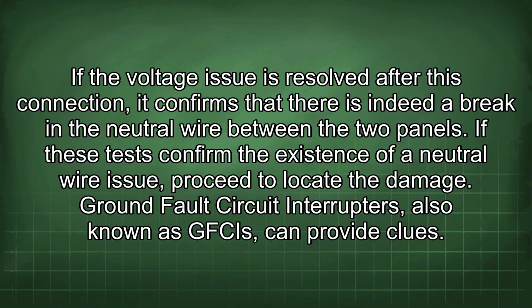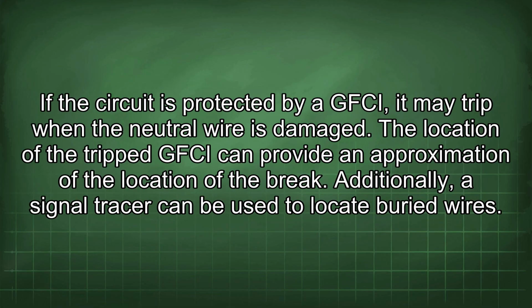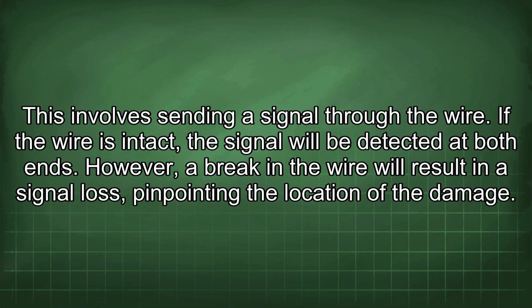Ground fault circuit interrupters, also known as GFCIs, can provide clues. If the circuit is protected by a GFCI, it may trip when the neutral wire is damaged. The location of the tripped GFCI can provide an approximation of the location of the break. Additionally, a signal tracer can be used to locate buried wires. This involves sending a signal through the wire. If the wire is intact, the signal will be detected at both ends. However, a break in the wire will result in a signal loss, pinpointing the location of the damage.